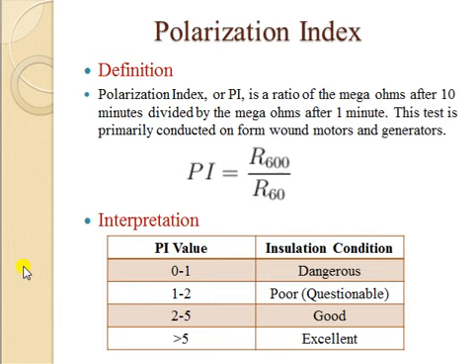The next test is the polarization index, or PI. Similar to DAR, you take a ratio — but here it is R600 divided by R60, that is insulation resistance at 600 seconds (10 minutes) divided by insulation resistance at 60 seconds. This test is primarily conducted on form-wound motors and generators. Interpretation: 0 to 1 is dangerous, 1 to 2 is poor, 2 to 5 is good, and greater than 4 or 5 is excellent insulation.